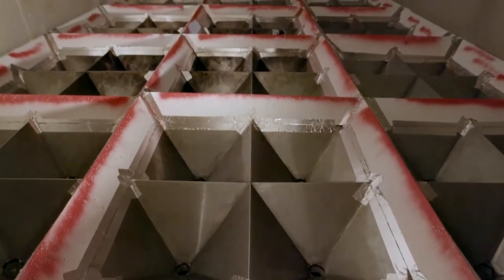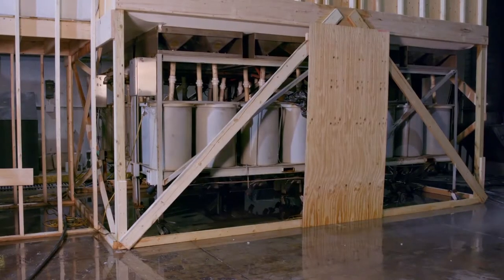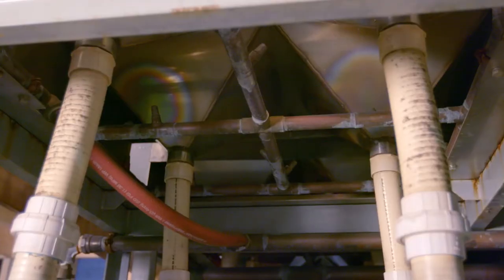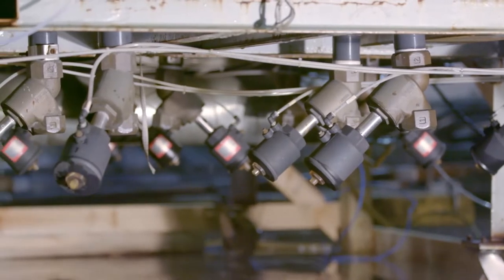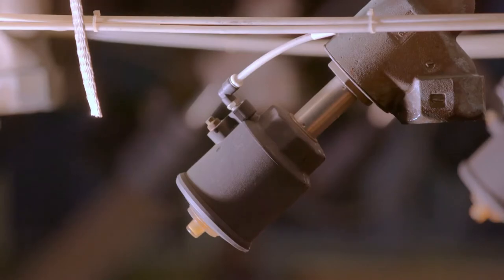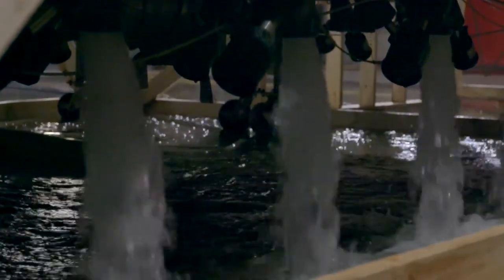I'm Adam Barrowy. I'm a research engineer in UL's Fire Research and Development Group. This week, we're using UL's actual delivered density apparatus, otherwise known as the ADD apparatus, to measure hose stream flow rates. Typically, this device is used to help sprinkler manufacturers design sprinklers by knowing where the water is sprayed during a sprinkler activation. So this week, we're just using hose streams and measuring the water by collecting it in these funnels, which run down into barrels, which are connected to pressure transducers, which ultimately allow us to calculate out flow rates within a given area.